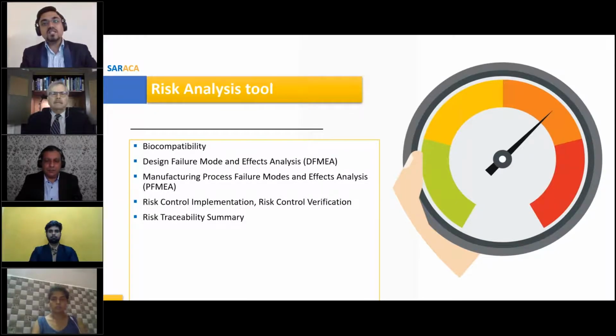So risk control implementation and risk control verification need to be done after this DFMEA and PFMEA. Then the risk traceability summary. Once you implement and verify, you need to trace the risks. You need to trace what risks were associated with which phase of the device, and the risks associated with the intended use of the device. Then clinical trials with the device: are there any risks associated with the clinical trials you have performed for your medical device?